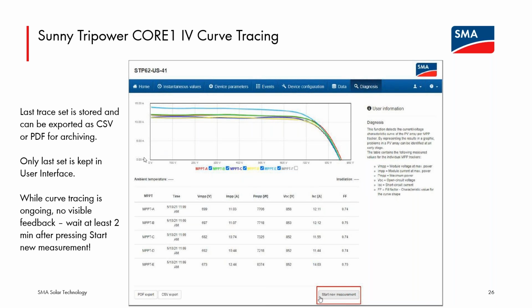If you have one inverter that has that and you do all of the curve traces for, let's say, 6 CORE1s fairly quickly, you can probably use those measurements for all 6, but they will only be logged for the inverter, or stored in the export in the inverter, where that sensor module accessory card is physically attached. But I think this is really nice. Again, it does not require disassembly of the array to have this be performed.